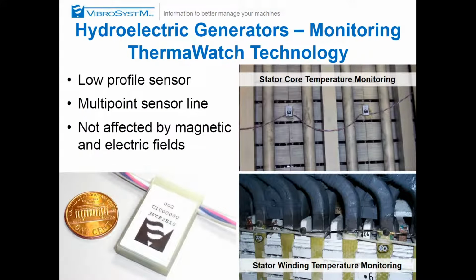Now for temperature, RTDs are fine, but they're notoriously susceptible to defects because basically they're installed in a very harsh environment. And for those who would still like to be able to monitor the stator bar, the stator core, the press fingers, well, any location associated with the core, the bars, you can use what we call ThermaWatch stator sensors, the digital sensors that provide their own temperature, so you can monitor the temperature of the core.